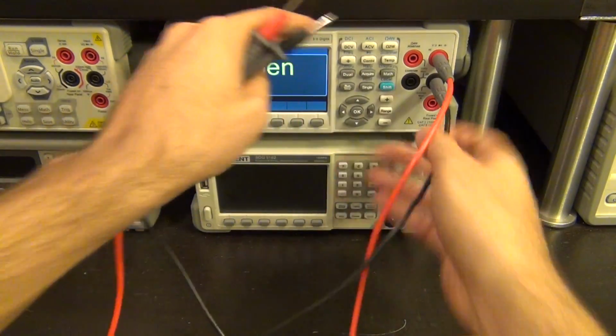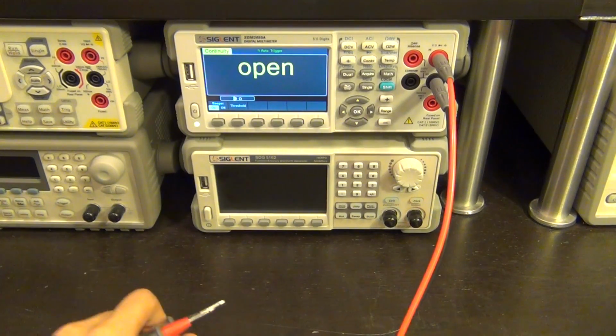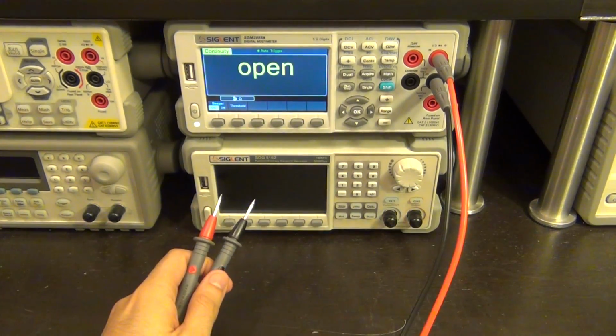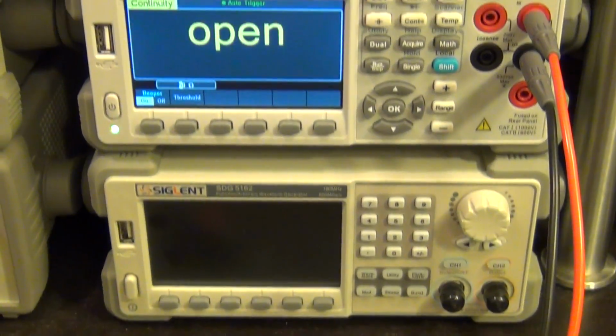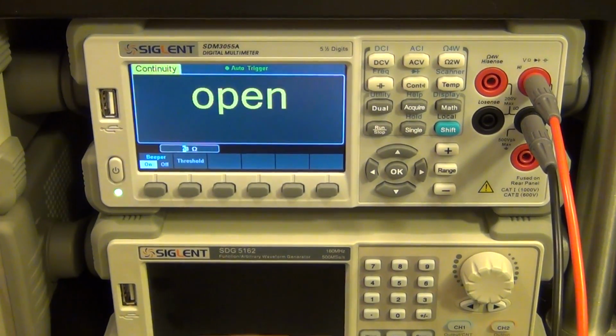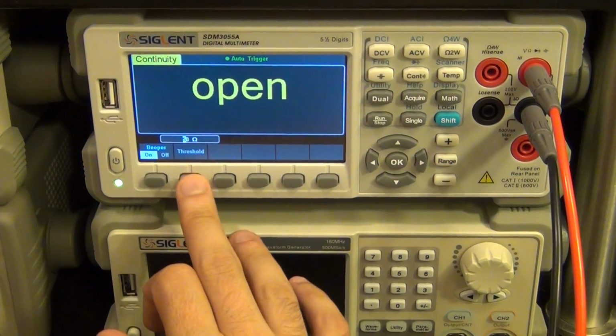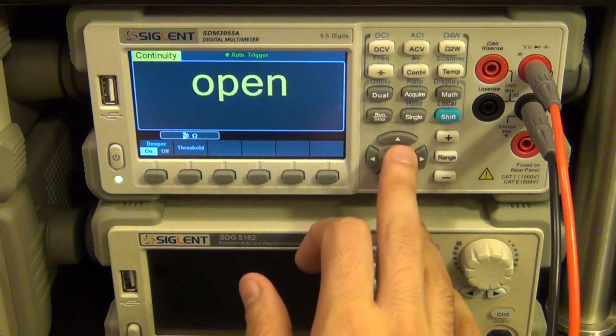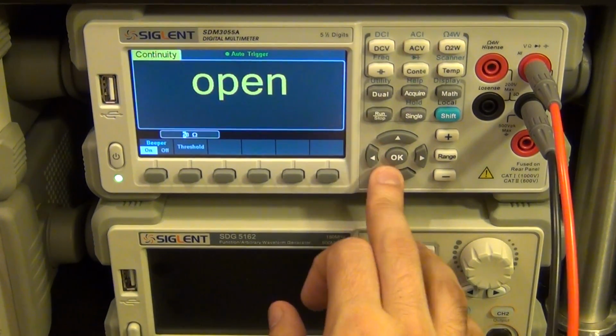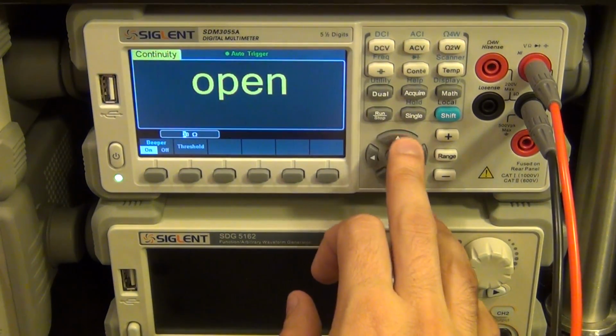So let's go ahead and plug that over here, and over here now we're in continuity mode. In continuity mode, one of the things you can do is tell the instrument what you want your threshold for continuity to be. Right now it's set to 50 ohms by default, and I can change it to whatever I want, like 20 or 30 ohms, it doesn't matter.